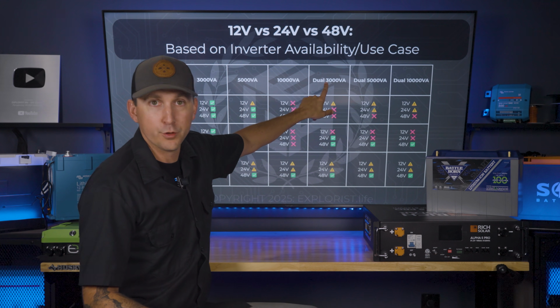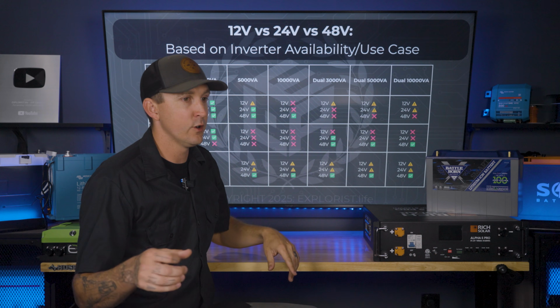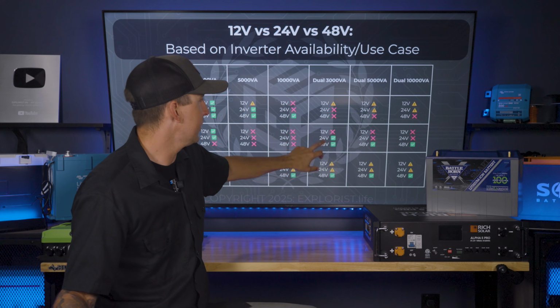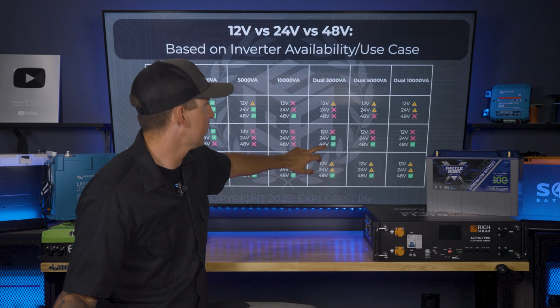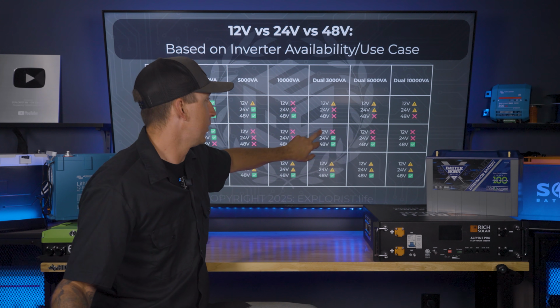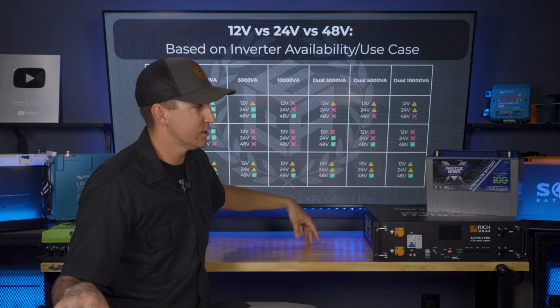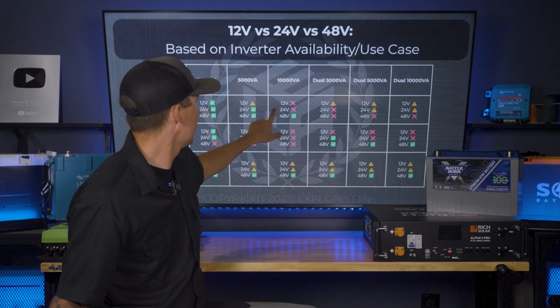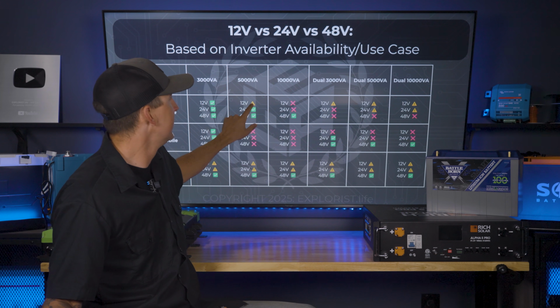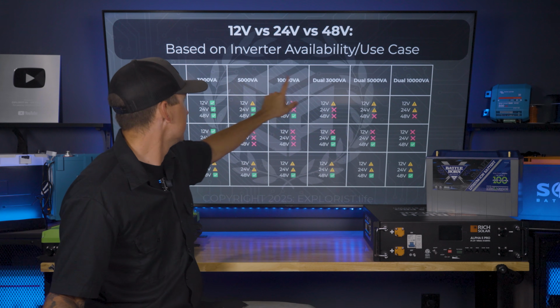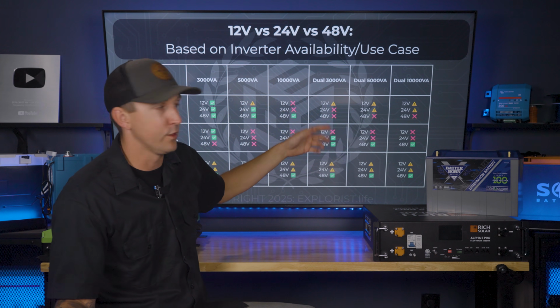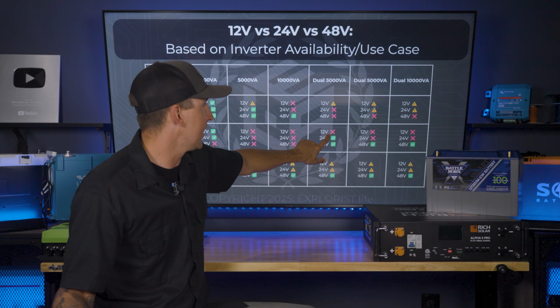We can do a dual 3 kVA system with single 4-aught wire, like we talked about earlier, with both a 24 and a 48 volt system. 12 volt sort of gets too many amps, similar to what we've got this exclamation mark for, but 6 kVA versus 5 kVA puts it over the threshold. So I've got a red X right there.